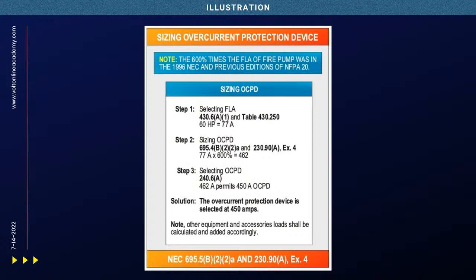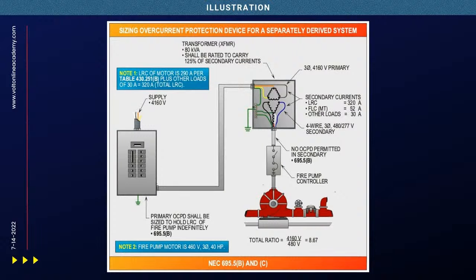That's 462 amps. And then when I'm sizing the overcurrent protection device, and how many times have you heard me say this, when you do a percentage, they've kicked this up quite a bit. But I said, if you're over 125%, any size over that, I size down. Well, what did I do here? I went to a 450 amp overcurrent device. Dude, freaking genius. Yeah. Now, watch this.